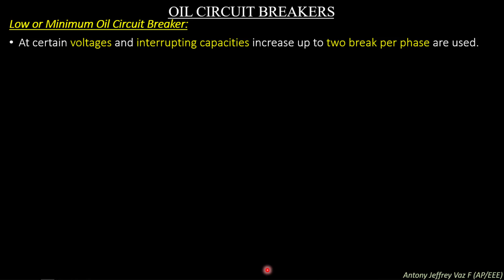Circuit breakers of this type can be used either outdoor or indoor and be mounted either on pedestal or at ground. So minimum oil circuit breakers can be used indoor as well as outdoor. So these can be mounted on the ground or at higher levels. At certain voltages and interrupting capacities, up to 2 breaks per phase are used. If we need to increase the interrupting capacity or interrupting voltage, instead of single break, 2 break minimum oil circuit breakers are available. Current transformers are incorporated in the portion of the tank. So to measure the current values passing through the breaker, a current transformer is present inside the circuit breaker itself.